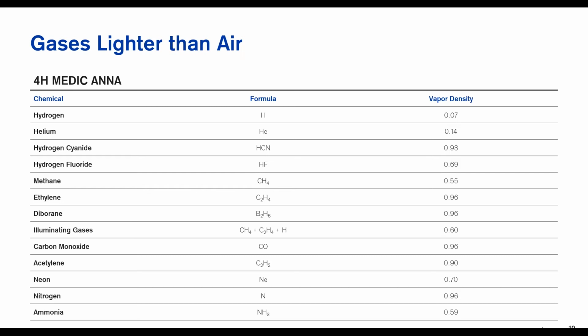And also understand that when you have a UEL situation, say I open up a confined space, I open the hatch or pull the cover off the opening, and my first reading shows I have a UEL situation, an upper explosive limit, up in the upper range, then I will always pass through that flammable range in order to get back to zero, back to the safe zone. So I open up that hatch, my initial readings may be high, I ventilate, whether by mechanical or natural means, whatever means of ventilation you want to use, my concentrations will start to adjust, and I'm already passing through that sweet spot, that flammability range, so keep that in mind. Most of your meters, if not all of them, should be intrinsically safe, but are your ventilation fans intrinsically safe? Are they rated for a flammable atmosphere, a potentially hazardous location? Understand that simply opening up that hatch or cover on a confined space may be all it takes to create that flammability range.